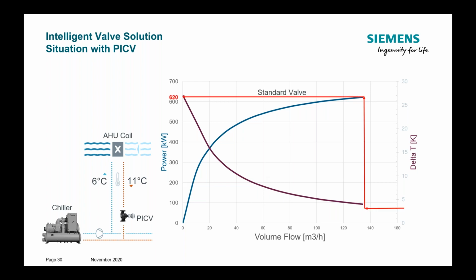But what about full load conditions? Here, with a standard valve, no flow limitation, flow will go up as far as it can. Let's assume 135 cubic meters. We will end up with a quite low DeltaT, around 4K. With the PICV, we have this flow limitation to the design flow. We have the 600 kilowatt power available on this coil with the 5 degrees DeltaT.